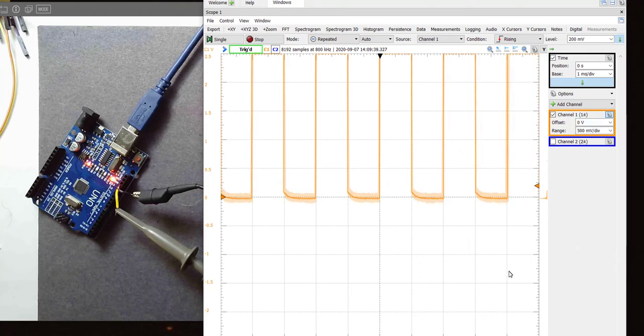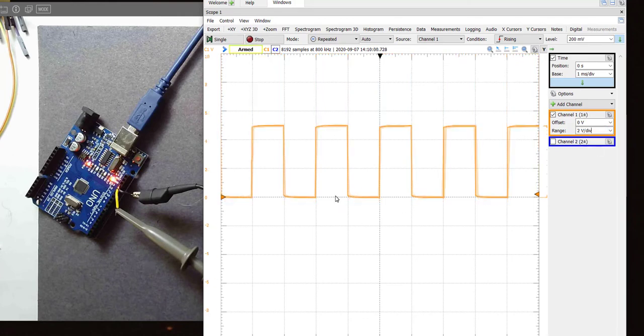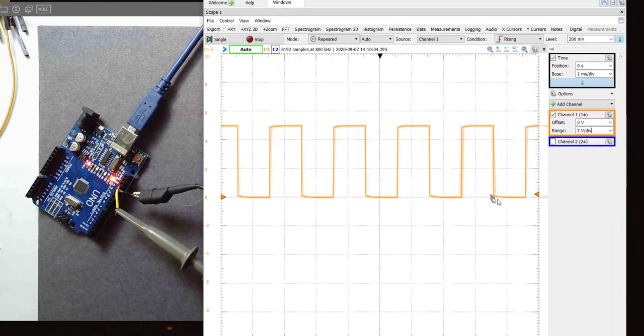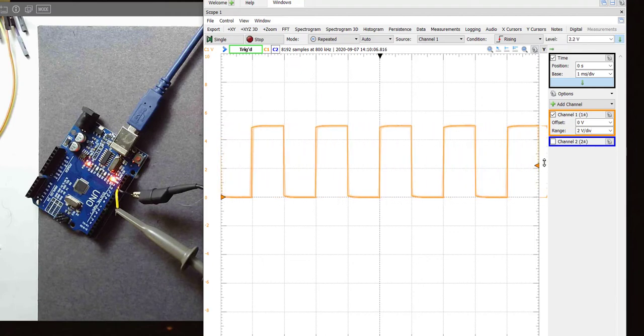And now we'll automatically do the conversion from whatever that tip voltage is. We want to display that tip voltage on the screen. We take the measured voltage, we scale it by a factor of 10 just to replot it, and now we're displaying the tip voltage on the screen. So let's bring that back on scale, and here's our 2 volts per division. And what we're seeing on the scale, and I have to adjust the trigger level here, is the tip voltage displayed. So really important to set that.